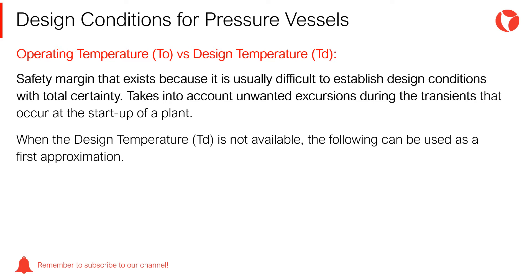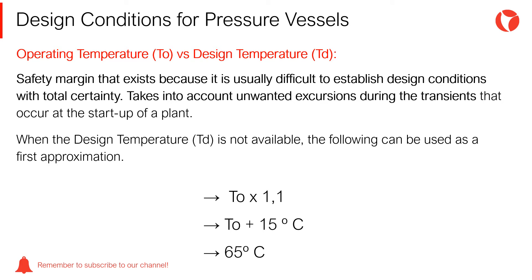The difference between the operating temperature TO and the design temperature TD is a safety margin that exists because it is usually difficult to establish design conditions without total certainty. This difference takes into account unwanted excursions during the transients that occur at the startup of a plant. When the design temperature TD is not available, the following can be used as a first approximation: TO plus 10%, or TO plus 15°C, or 65°C as a minimum.